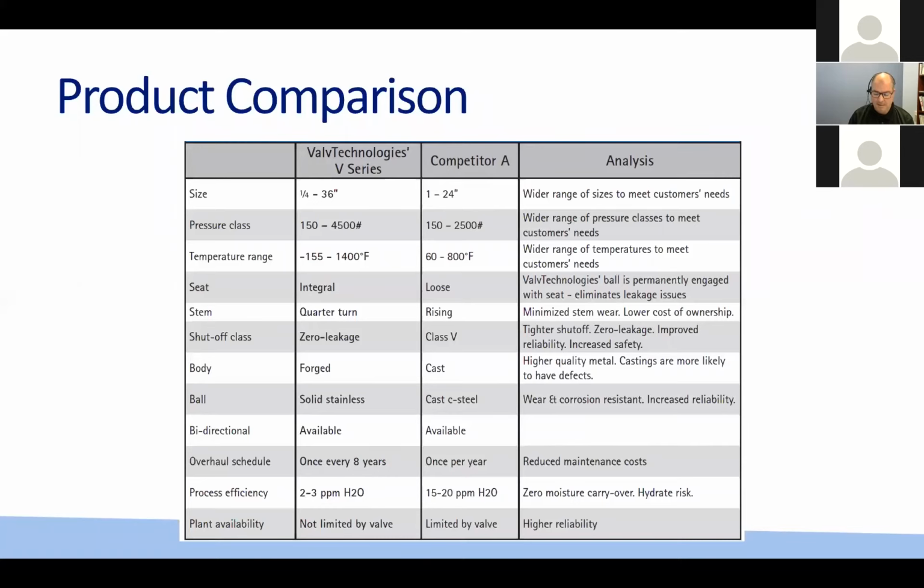But if the coating has worn so much that it's not isolating and kiss lapping is not successful, then we can blow it off or blast it off, but typically we'd have to replace the ball and seat as a set. And then packing is really straightforward. We can replace the packing in the valve. We can replace the loose upstream seats or the ball valve spring. But if the coating has worn to such an extent that it's not repairable, then we'd have to replace the ball and the seat.